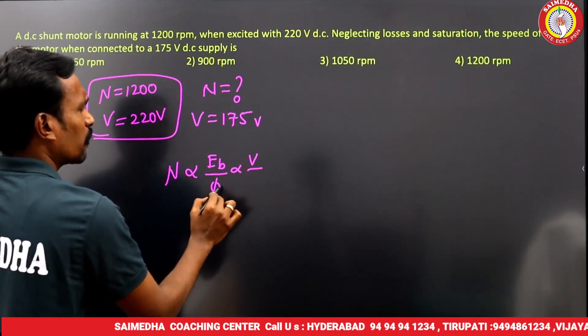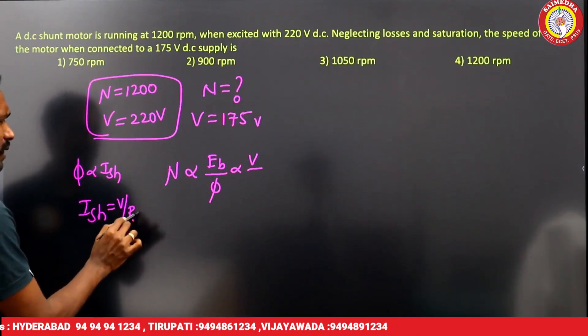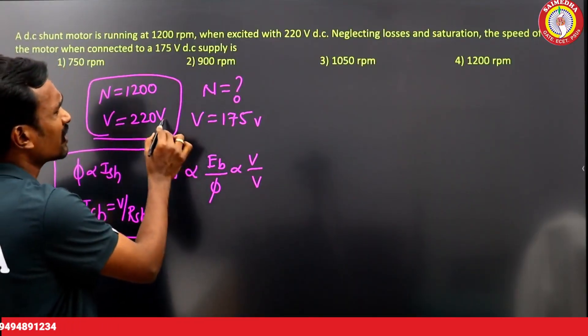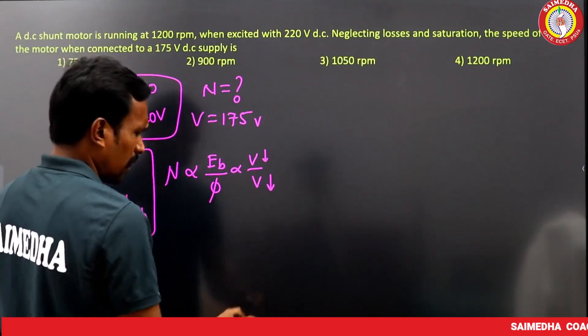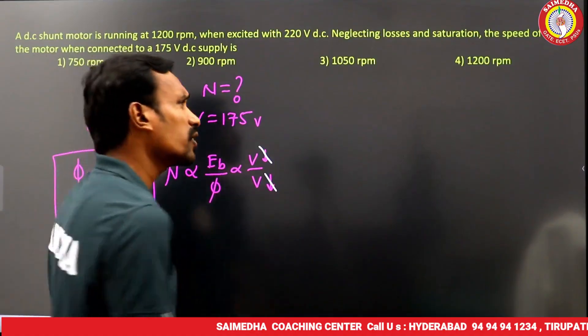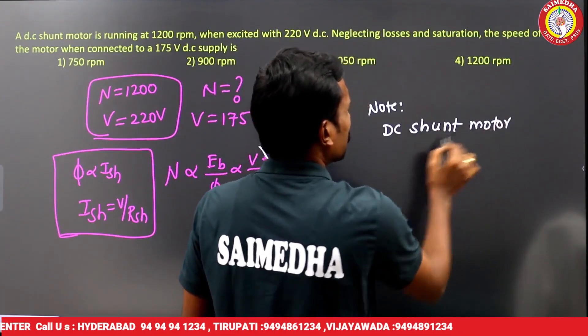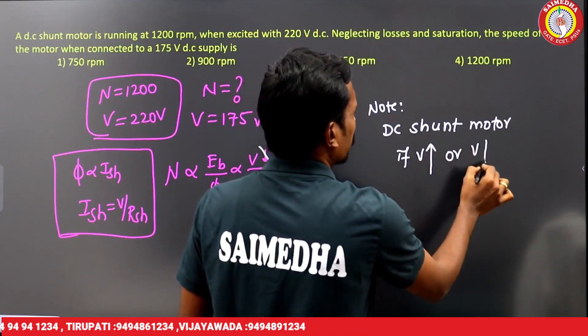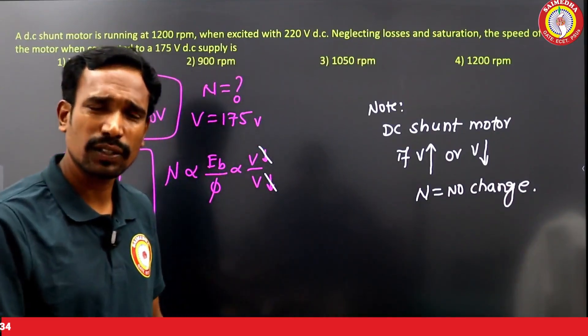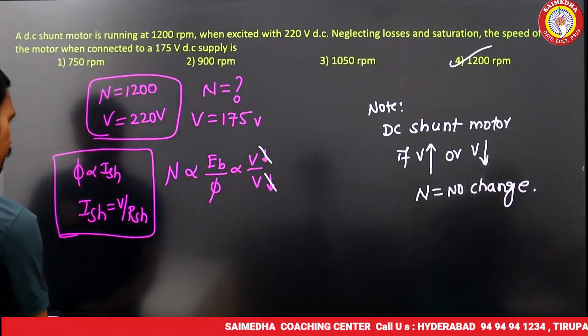In a DC shunt motor, speed is proportional to Eb/φ. The field current Ish = V/Rsh, so φ is also proportional to V. When voltage changes, both Eb and φ change by the same factor — they cancel out. Therefore, voltage changes have no effect on speed in a DC shunt motor. The speed remains 1200 rpm.